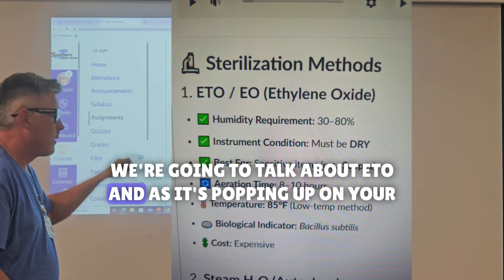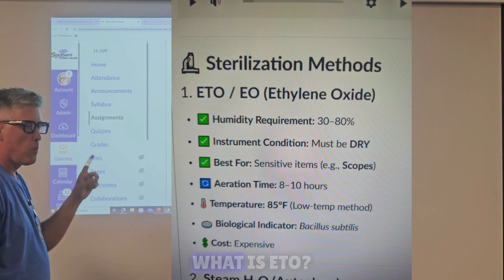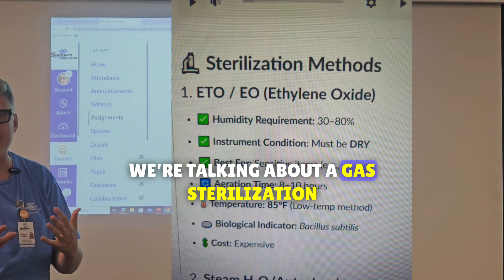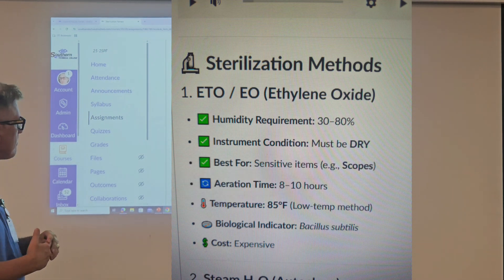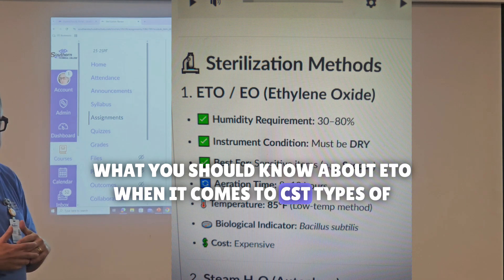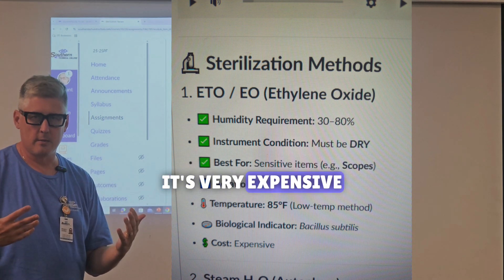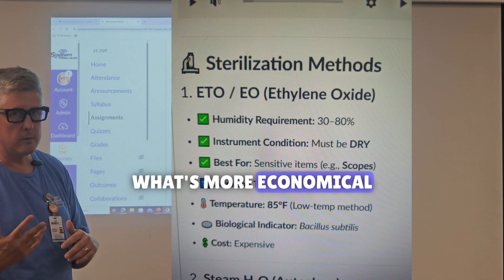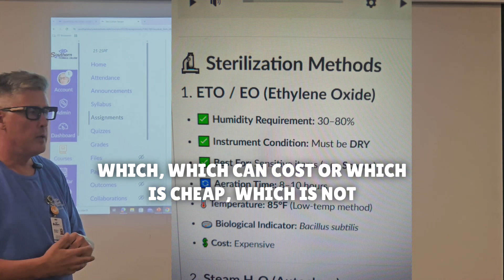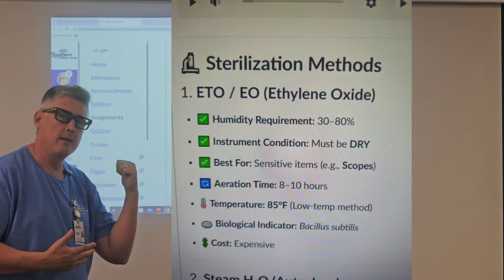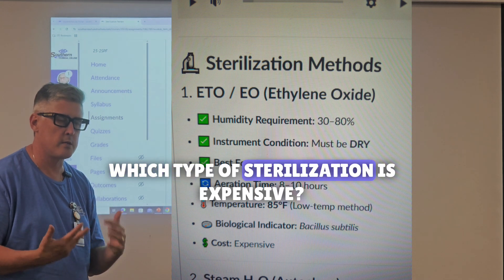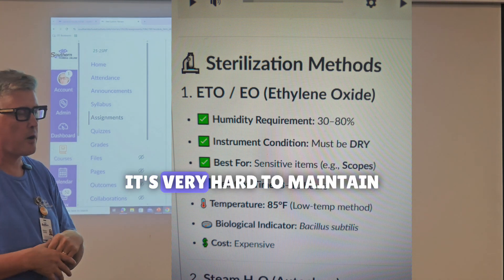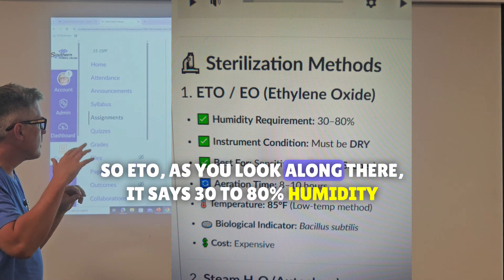What is ETO? ETO is ethylene oxide — we're talking about gas sterilization. What you should know about ETO for CST questions: it's very expensive. There are questions revolving around which sterilization is more economical, which is cheap, which is not. If a question asks which sterilization is expensive, ETO is it. It has a lot of gas and it's very hard to maintain. Looking at the list, ETO requires 30% to 80% humidity — that's what it takes for ethylene oxide sterilization to work.